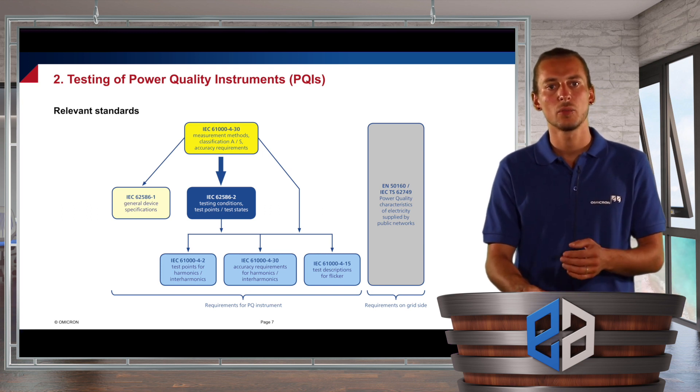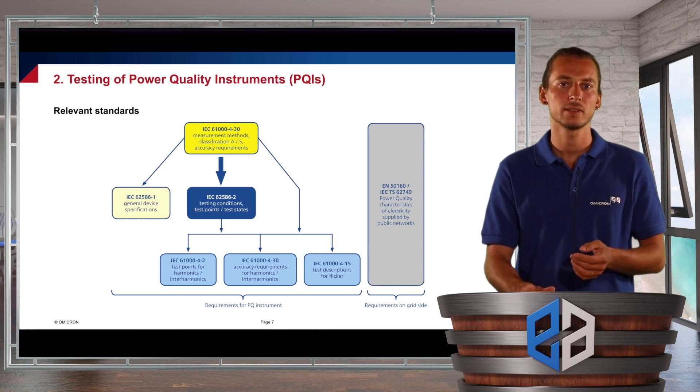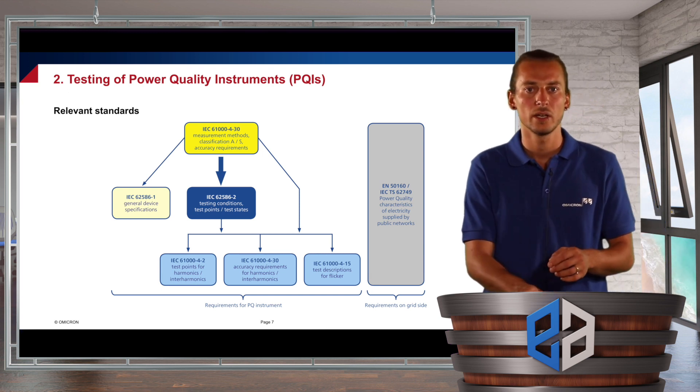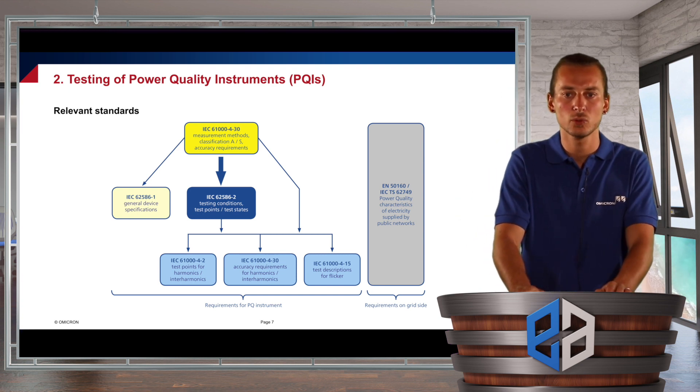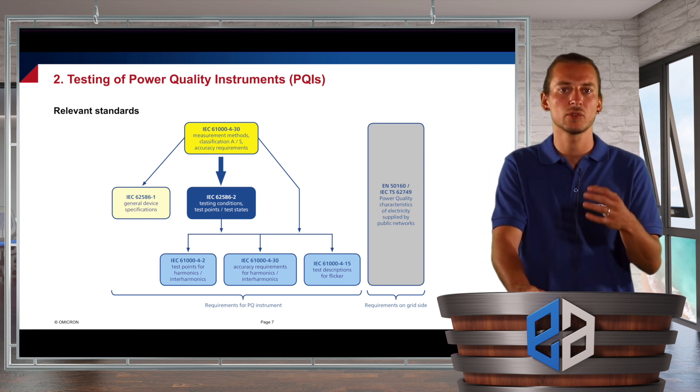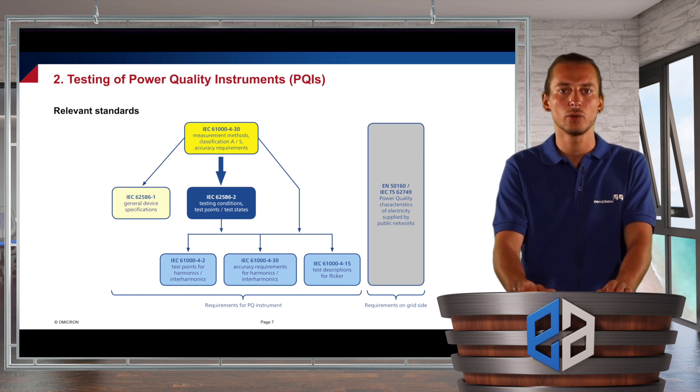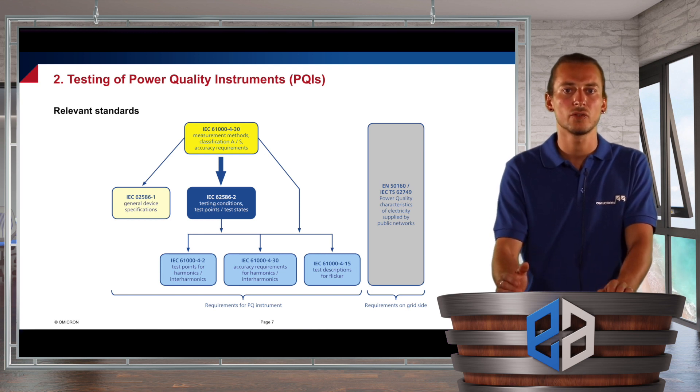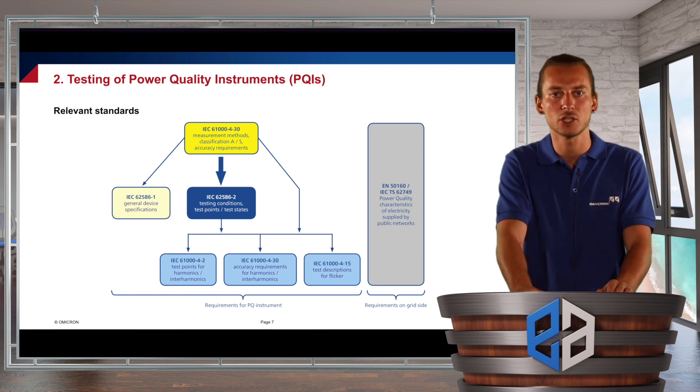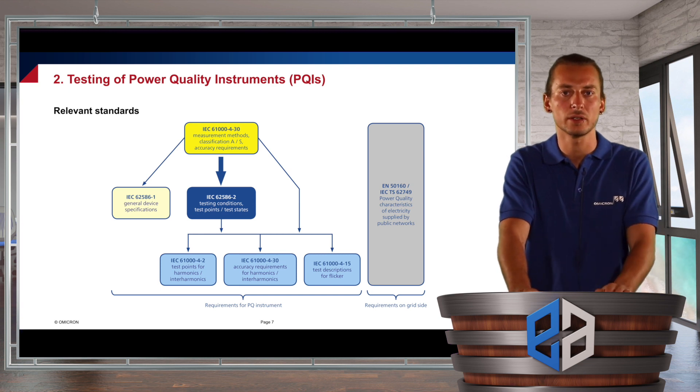Then this standard points out to the standards IEC 62586-1 and dash 2. And there, especially the dash 2, is very important when it really comes to testing of power quality analyzers. Because within this standard, there are the real test signals, test conditions and test points defined, which have to be injected when you do a power quality test.